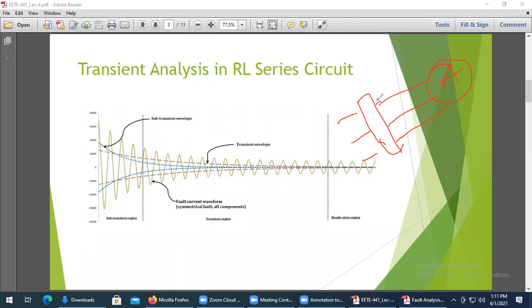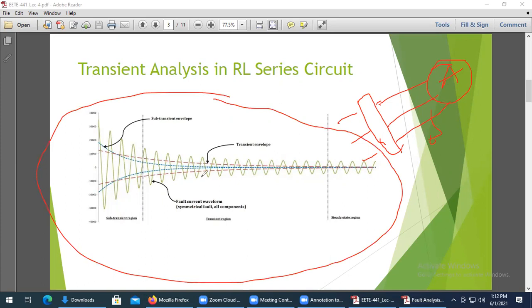So what we do, being a power engineer, is normally analyze it - we simulate or calculate it in different ways, like for single line to ground fault, double line to ground fault, symmetrical fault, considering all these parameters. Then we analyze these fault currents, and associated with this fault current we can calculate the short circuit capacity, breaking capacity, making capacity, and then properly go and buy a proper circuit breaker. So though we deal only with protective devices, it is essential that you must know about this analysis part also, because without proper analysis you can never be able to select a proper switching device for protection.